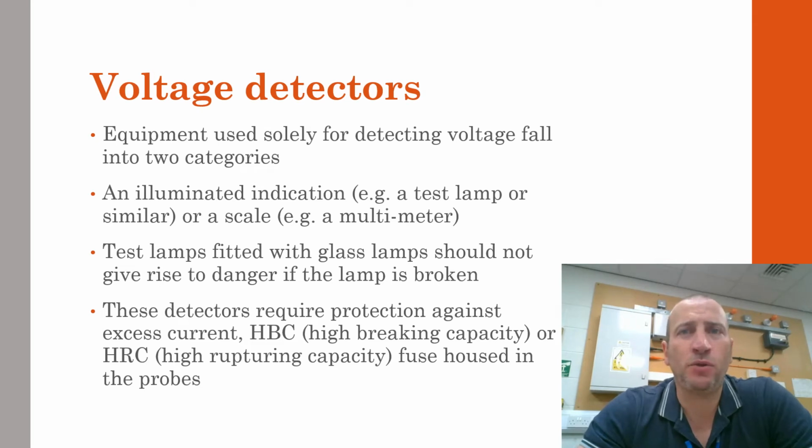All these detectors require protection against excess current. This protection is usually provided by an HBC fuse, that is a high breaking capacity fuse, or an HRC fuse, which is a high rupturing capacity fuse. These will be housed within the probes themselves.